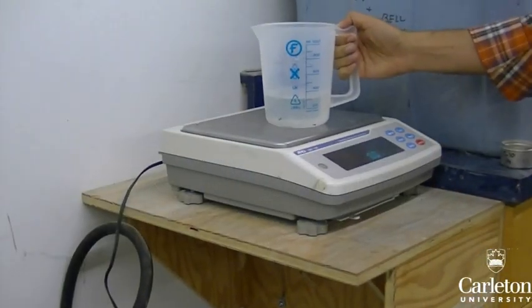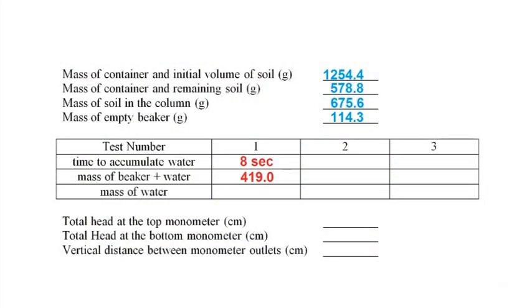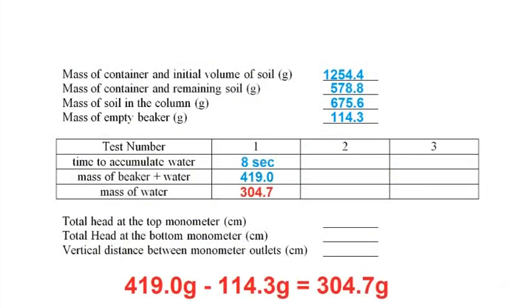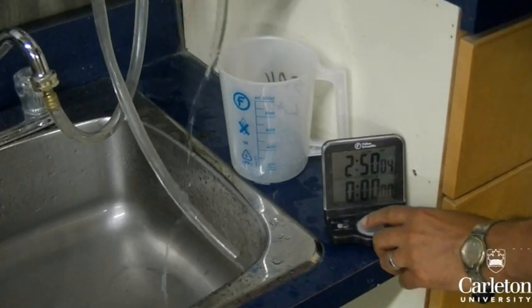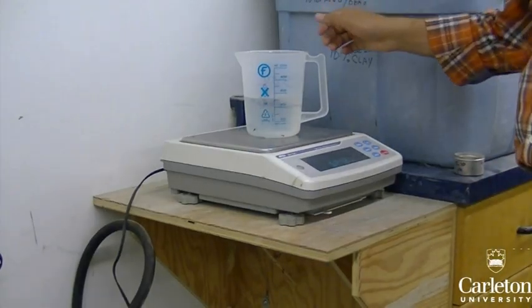Now record the mass of the water plus the beaker as well as the time it took to fill in seconds. Empty the water and zero the stopwatch to reset. Repeat this test two more times, each time aiming for a different amount of water.